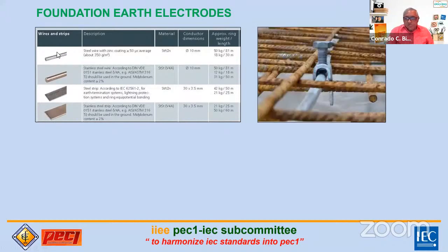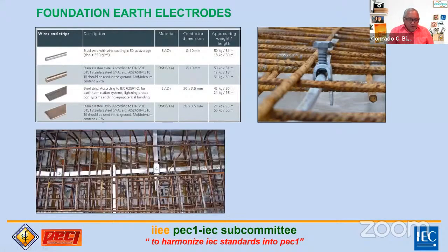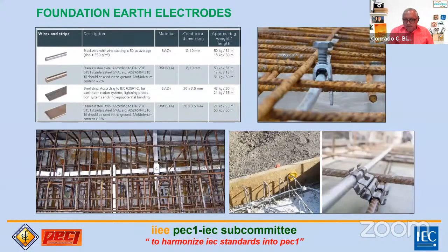And here's the application: you have reinforcing bars, then this steel wire is used and clamped onto the foundation rebars. There are also steel strips used, all banded together with special connections for these earth electrodes, before the concrete is poured.